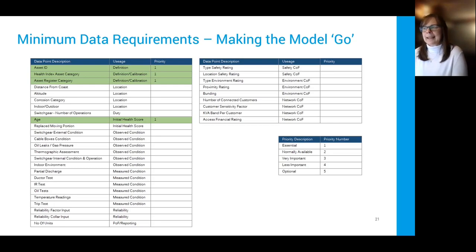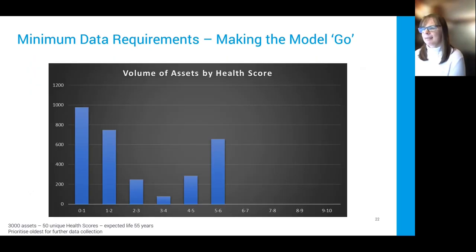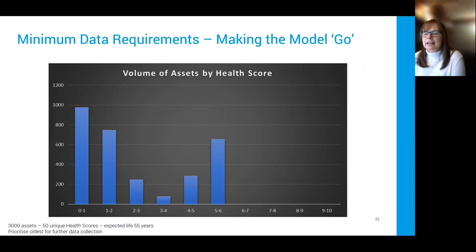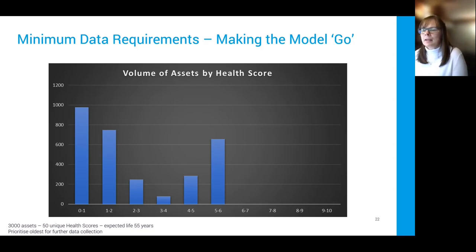What makes the model go: you always get a result as long as you have an identifier, a category, and an age — that's the absolute bare minimum but only gives you an age-based condition. With our 3,000 assets, we end up with about 50 unique health score values. The expected life is about 55 years, so that's approximately the limit of the minimum dataset. But that's still really useful because you can prioritize your data collection based on your oldest assets.